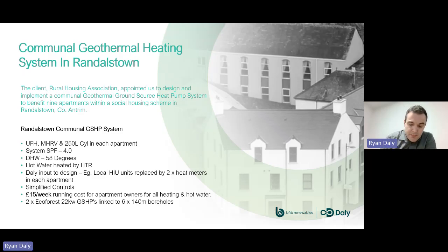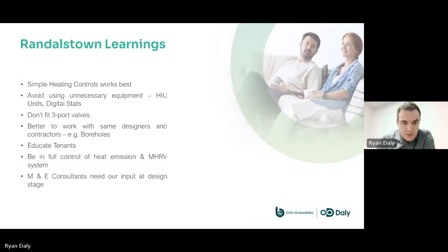We also put forward very simple controls for the homeowner. They have one master stat in their hallway, which is simply up or down, and then they hit a tick, and that's how they set their heating. So there's only one stat in each apartment. The running cost to date is averaging around £15 a week for the winter months, and that's all their heating and hot water, which they're very happy with.